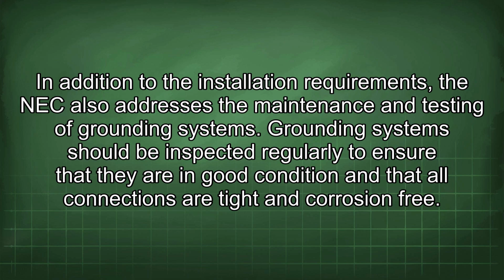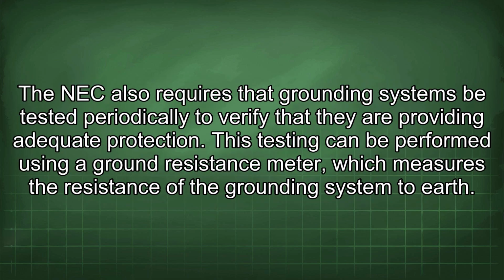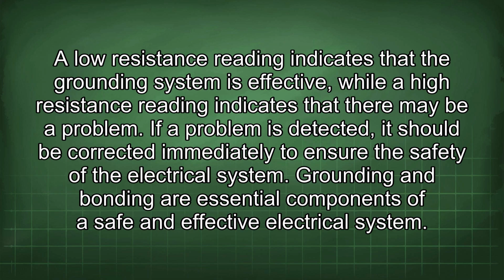In addition to the installation requirements, the NEC also addresses the maintenance and testing of grounding systems. Grounding systems should be inspected regularly to ensure that they are in good condition and that all connections are tight and corrosion-free. The NEC also requires that grounding systems be tested periodically to verify that they are providing adequate protection. This testing can be performed using a ground resistance meter, which measures the resistance of the grounding system to earth. A low resistance reading indicates that the grounding system is effective, while a high resistance reading indicates that there may be a problem. If a problem is detected, it should be corrected immediately to ensure the safety of the electrical system.